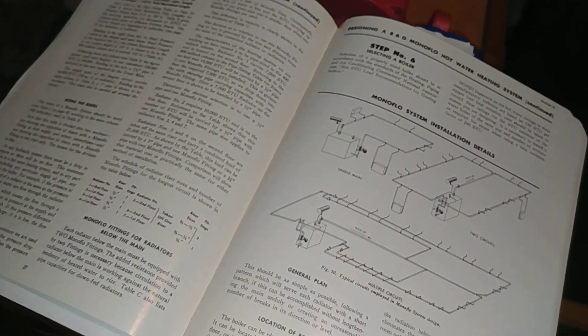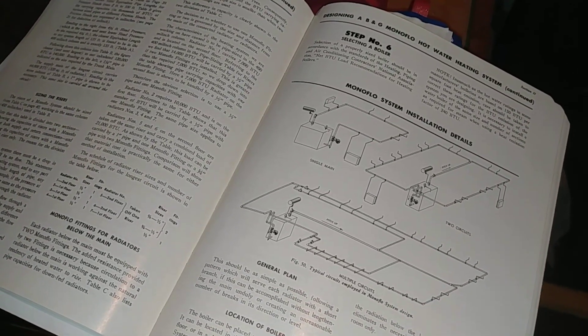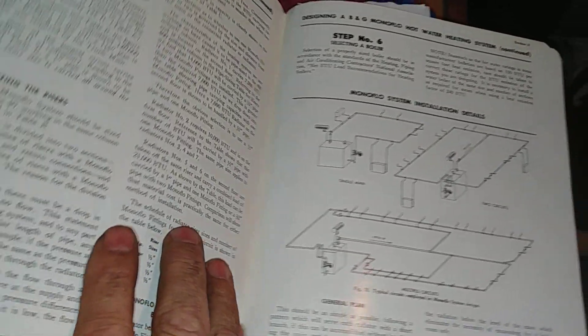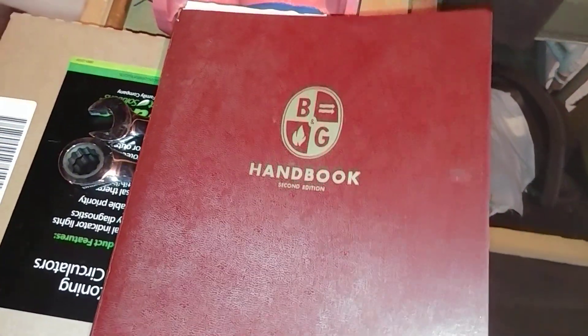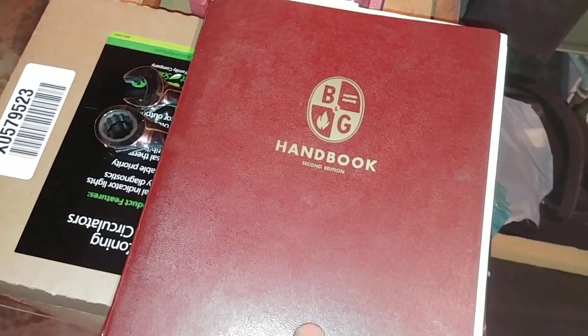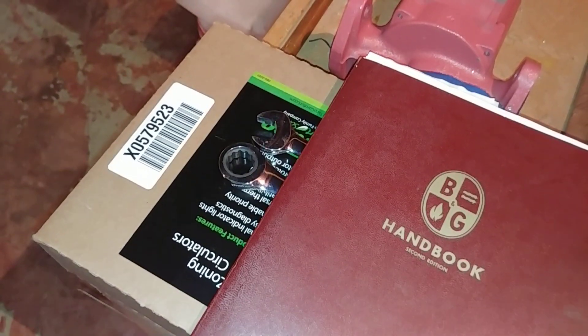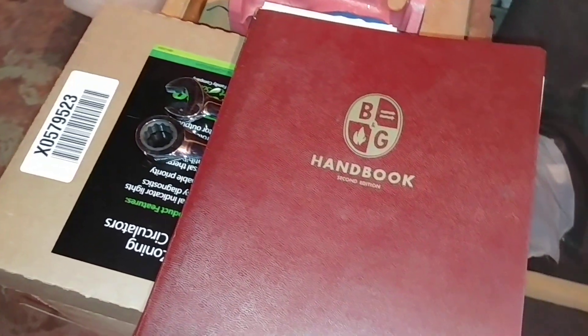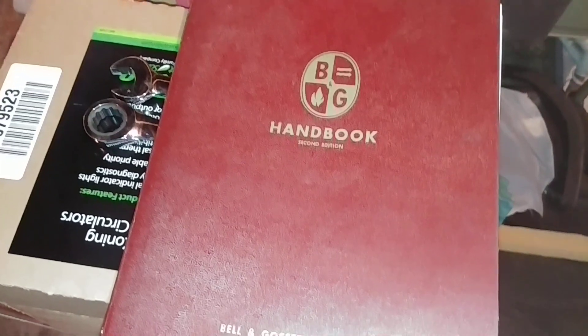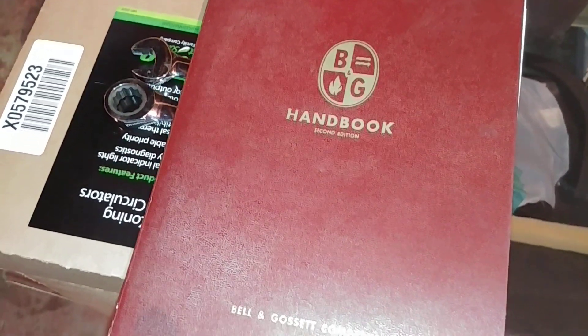I hope this is useful. If you have a customer who doesn't have enough heat coming out of their units because they have a monoflow system, you want to look for the proper size circulator, and you want to look for improperly capped-off monoflow or venturi tees. Thank you very much for your support, and I'll see you on the next one.